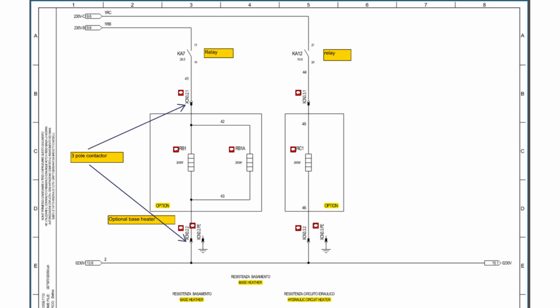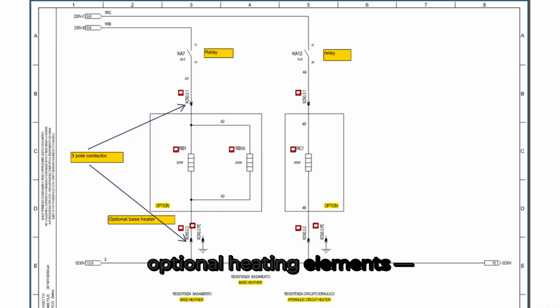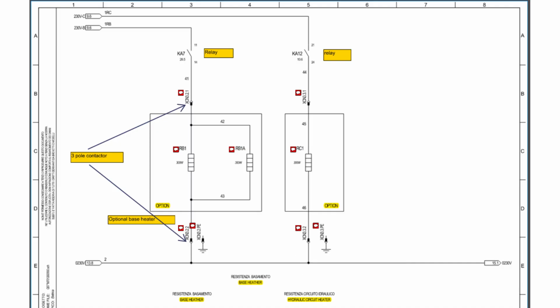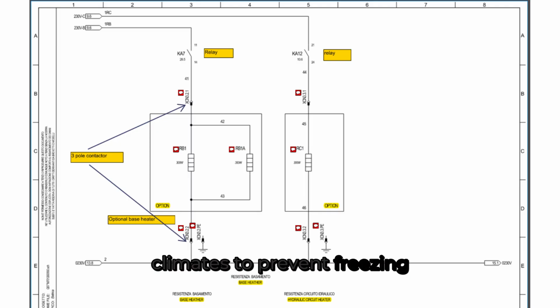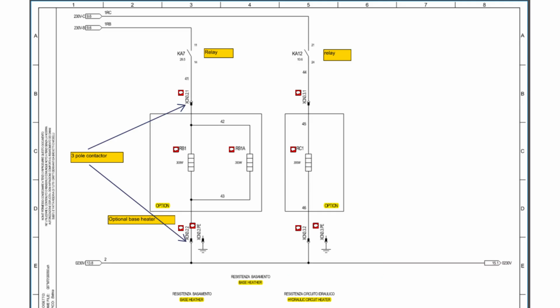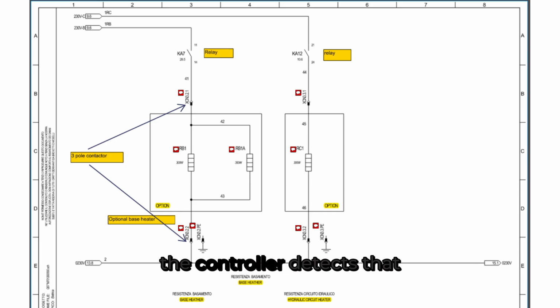This page continues with the 230-volt control power, and it covers the optional heating elements, the base heater and the hydraulic circuit heater. These are installed in units operating in colder climates to prevent freezing and ensure reliable startup during low ambient conditions. Starting from the left, we see the power feed labeled 1RC and 1RB, both 230V lines supplying this section. The first control device is the relay Ka7, which acts as the switch for the base heater circuit. This relay energizes when the controller detects that the ambient temperature has dropped below a certain threshold.